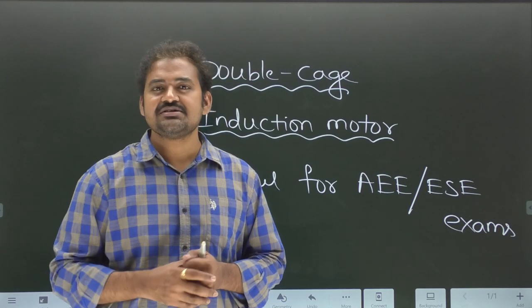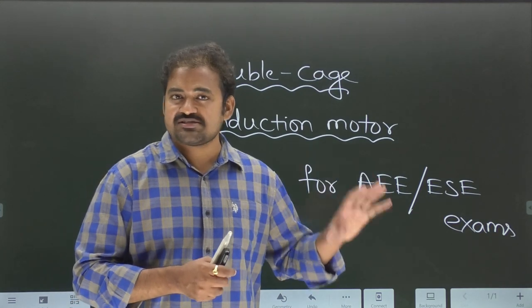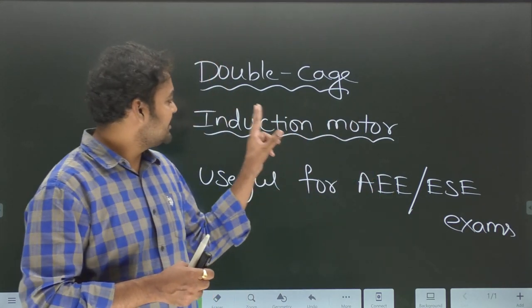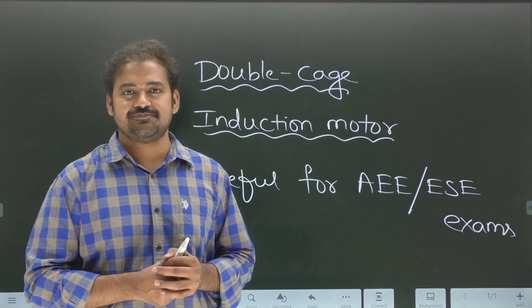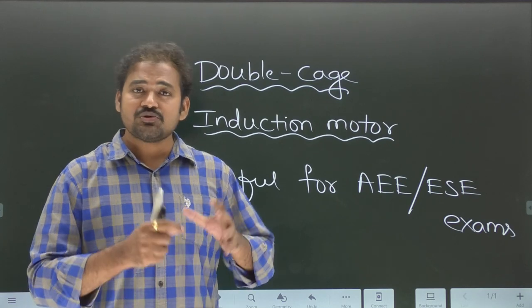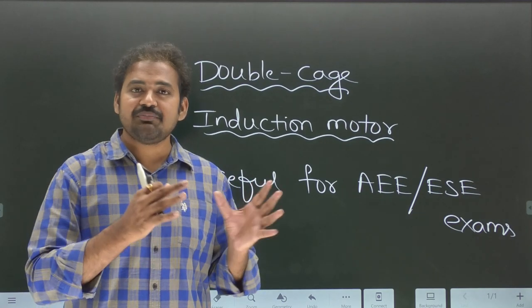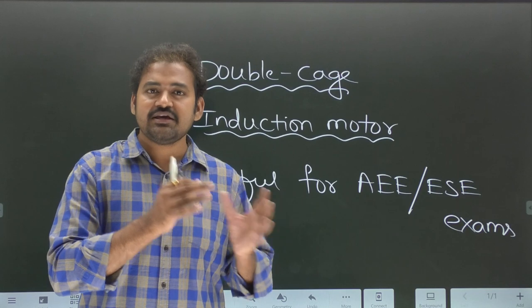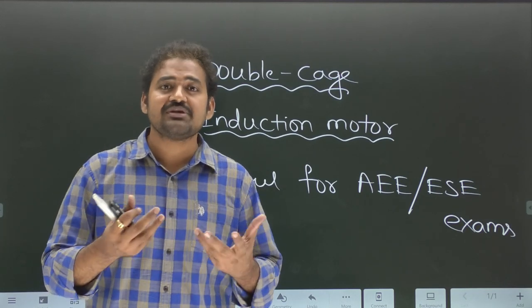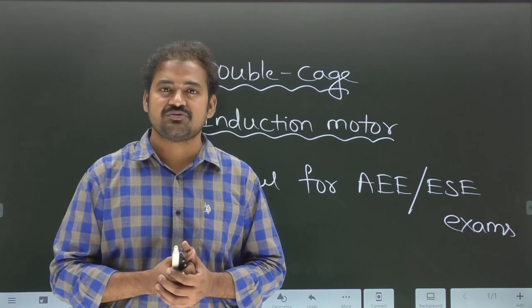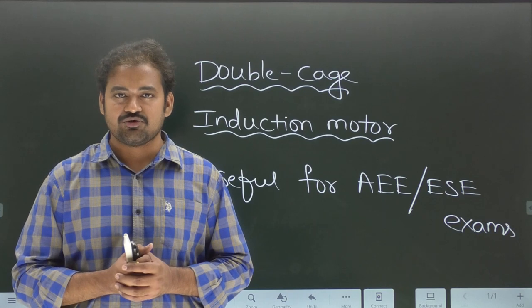Whereas in slip ring induction motor, we can add additional resistance in series with the rotor so that higher starting torque is possible. This is the reason why for all high starting torque applications, slip ring induction motor is preferred. Therefore, the disadvantage with normal squirrel cage induction motor is it cannot be used for high starting torque applications. To overcome that disadvantage, we have a special design known as the double cage induction motor design.